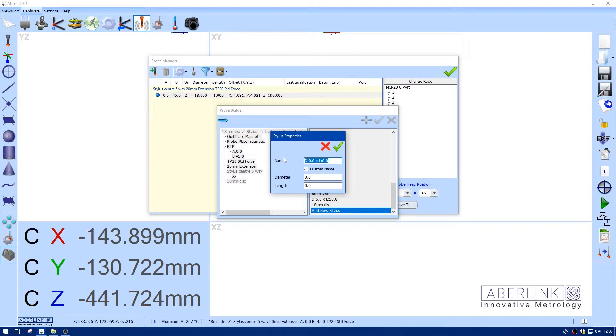Again, I'm going to give it a custom name. Now the diameter is the measurement I took over the stud. In this case it was 3mm. And the length is the distance from the center of the stud to the center of the stylus.